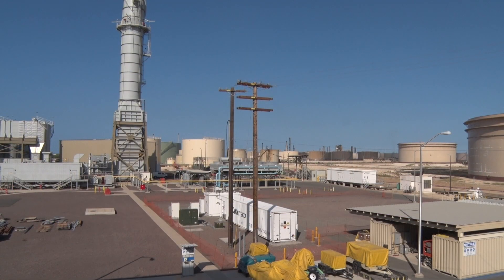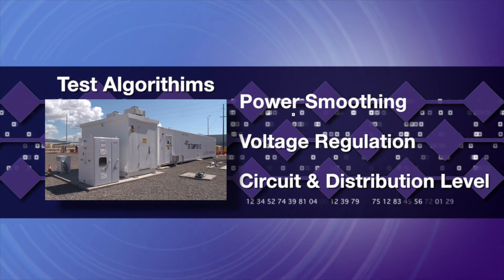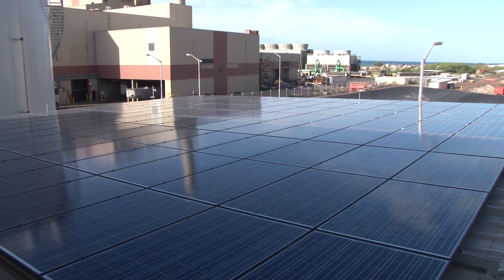Another important aspect of the project is the development and testing of algorithms that will advance the support for larger battery projects in the future. The purpose of the project is to evaluate how substation-sited battery energy storage could help mitigate operational issues at the circuit and distribution level. The battery project will be testing several control algorithms: power smoothing and voltage regulation at the circuit and distribution level, and frequency response at the system level. We hope to see how this battery can mitigate PV impacts and determine if we can deploy this on a commercial basis.